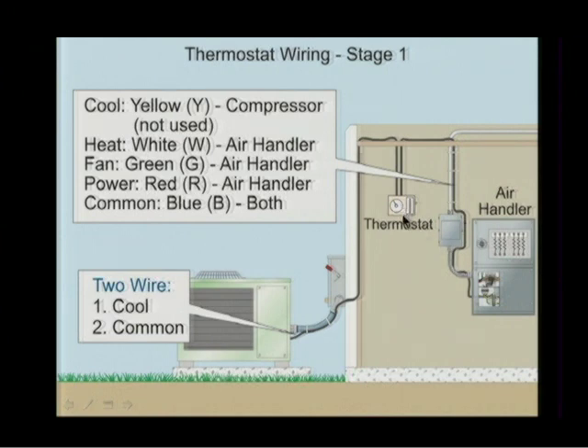So let's just take our time. I guess the standard is your thermostat is going to have a yellow terminal, and that'll be identified for the yellow wire. That's usually what the Y means. The thermostat will have a W terminal. That would be for the white wire. It will have a G terminal for the green wire if you use color coding. If you actually use these colors. And it will have an R terminal for the red wire. And it will not have a terminal B at all for the common. It's just going to have yellow, white, green, and red. And this is a single-stage, simple thermostat, not 2-stage.